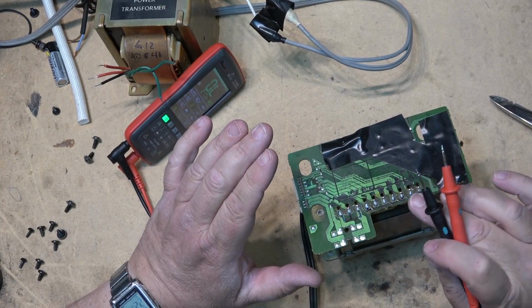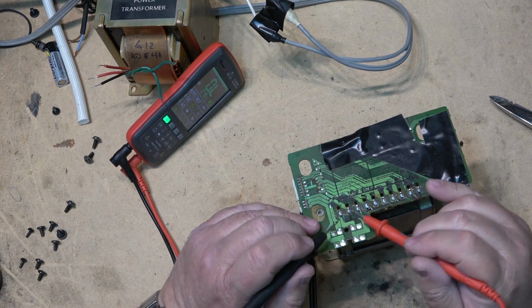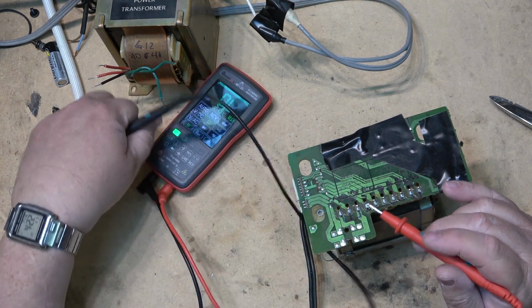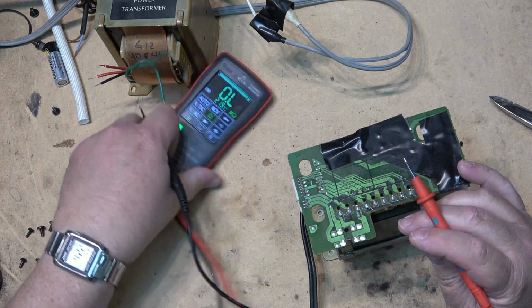So if we look at this transformer, this one actually has 3 separate windings. You've got one winding here, which is the center tap. We can confirm that if we look at the meter in ohms mode.